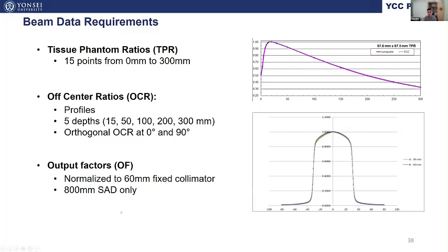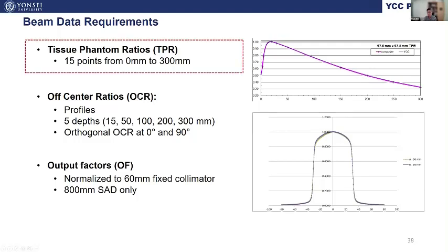Beam data required for the Precision and MultiPlan TPS beam modeling include output factors, profile shape, and TPR data, similar to the other TPS, but beam data acquisition may take a little more time as the beam modeling is based on the TPR data rather than PDD. So for your convenience, we recommend acquiring the PDD data as part of the beam data commissioning so that it can be used for the periodic QAs afterwards instead of TPR.